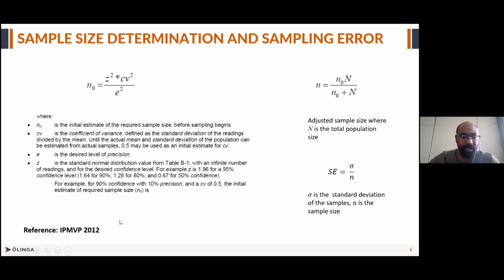The next few slides, the reference for them is the IPMVP 2012 version. I'm not sure whether they've released a later version, but if you go into the IPMVP and check Appendix B, it presents some of this. So you have your Z value, which is your confidence level. An example that's typically followed in our M&V practice is 80/20, where you have 80 confidence and 20 precision. You take that 80, put it into the normal probability graph, and you get your Z value of 1.28. Your CV is the coefficient of variation of your samples.